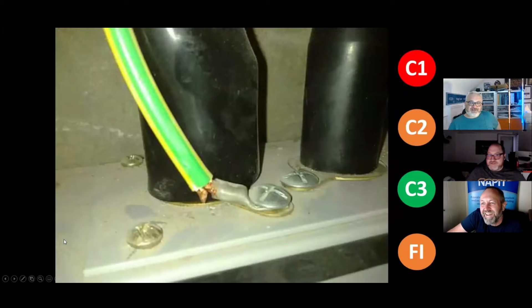So again, it's a sub-main feed. Very good eye on the inspector. I got sent this - there's just some cores not on it. It's a separate CPC which they've terminated. So they've run an armoured cable with a separate CPC, which isn't uncommon in a lot of places. Designers require a separate CPC.